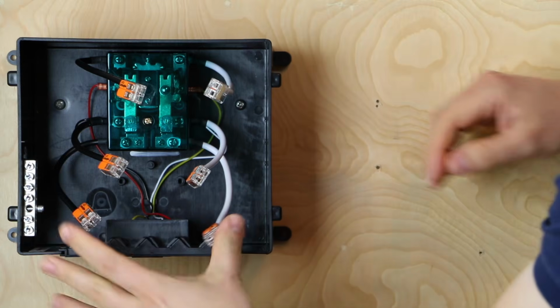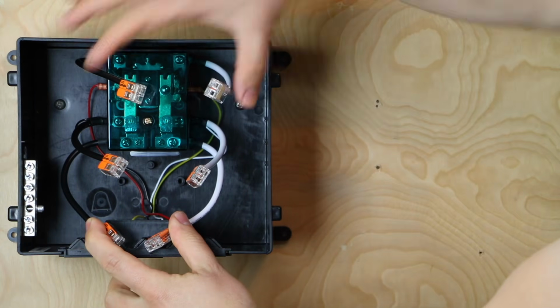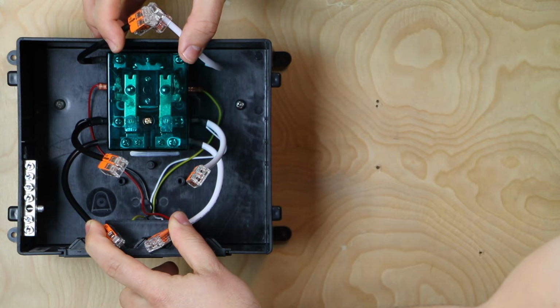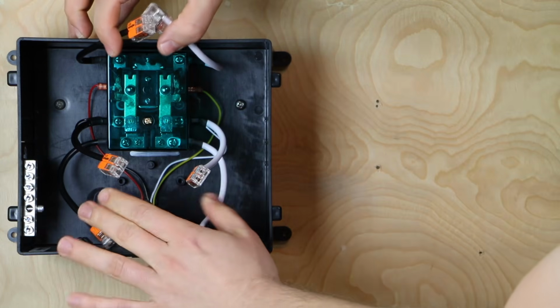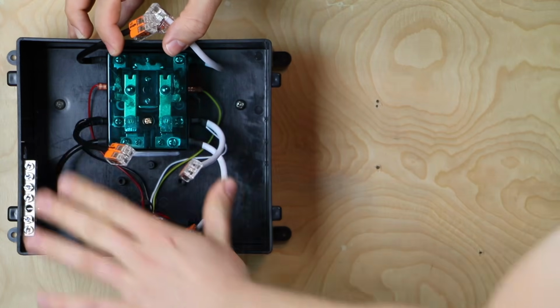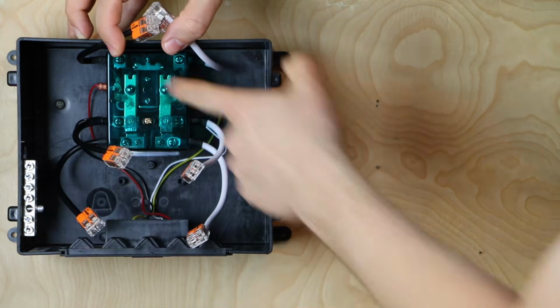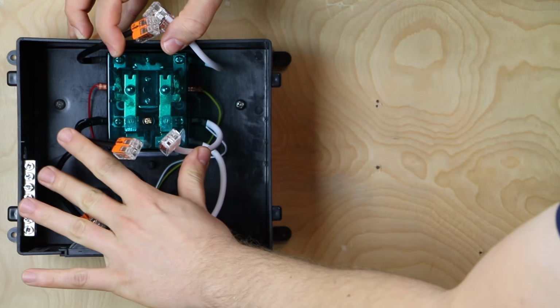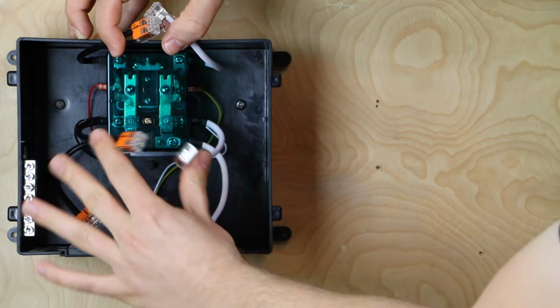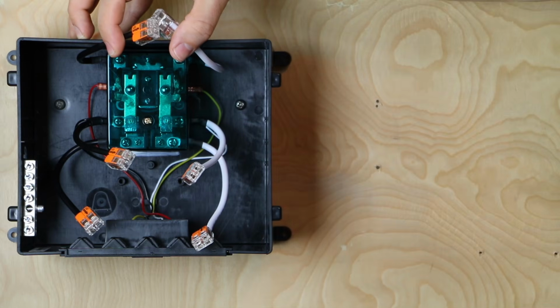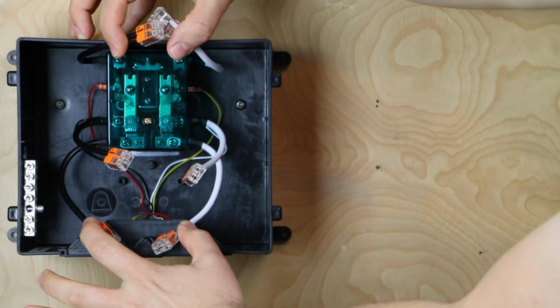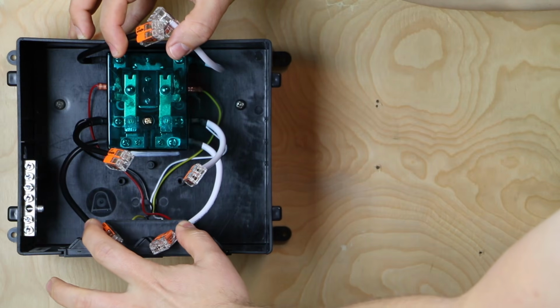So the inverter is going to come in here, and by default it's going to feed our breaker panel, while the power grid comes into this middle pair. When it's available, after a 30-second delay it's going to pull power from the power grid and send that to our panel, and quit taking power from the inverter.